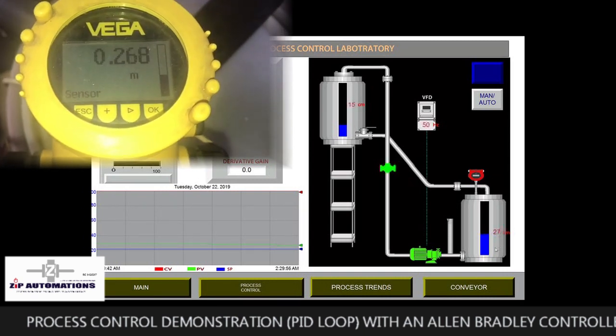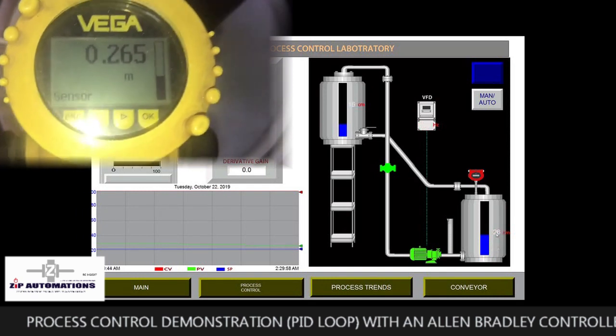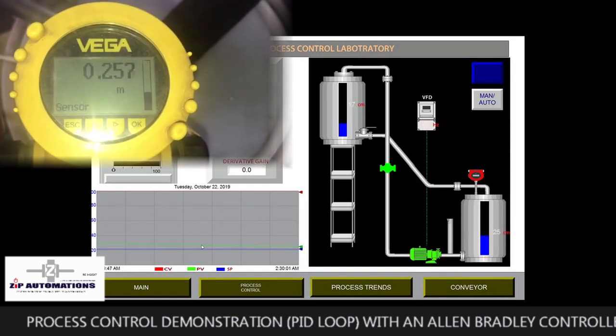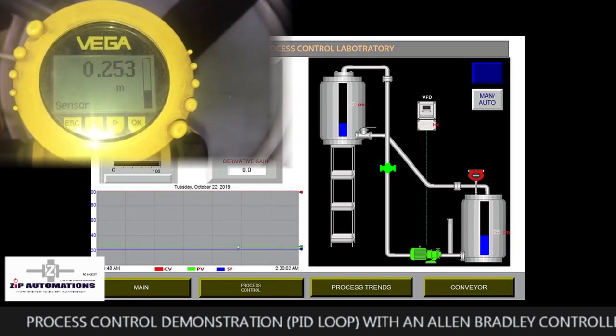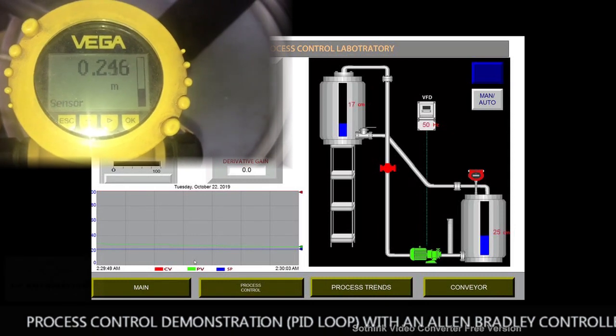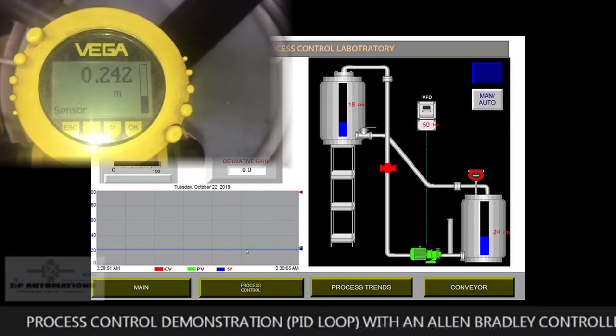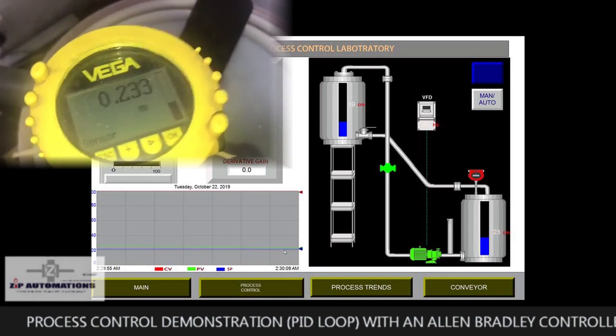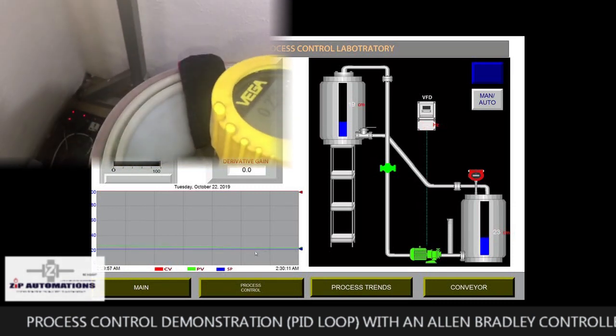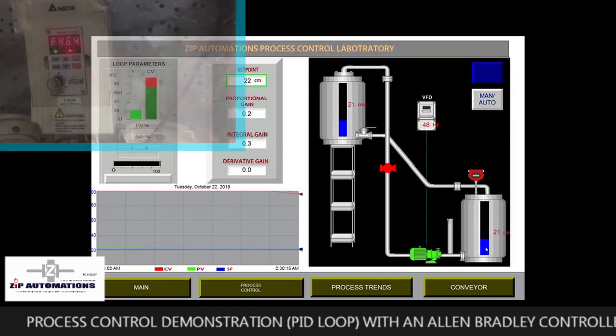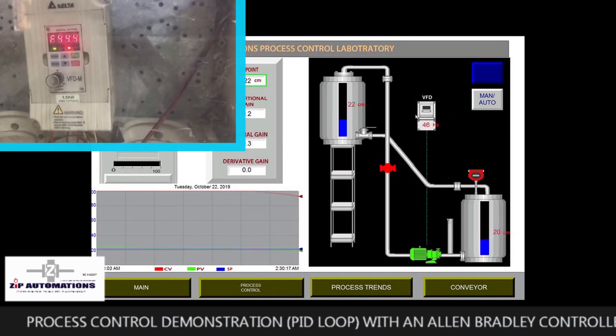We can see the level is reducing. This green line here is the process variable and it's trying to get to the set point of 22cm. I've gotten to the set point. You can see the VFD is ramping down, trying to shut it down.